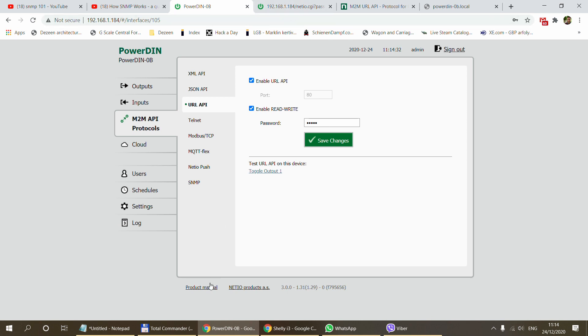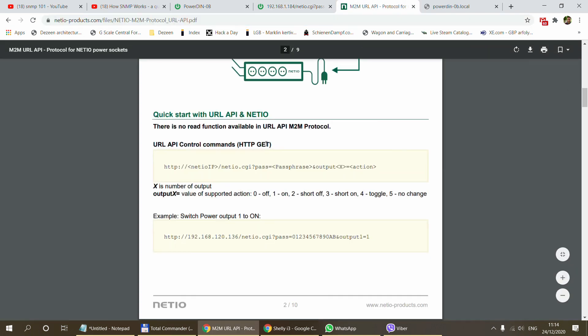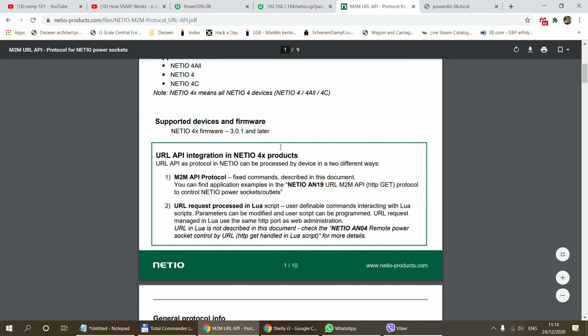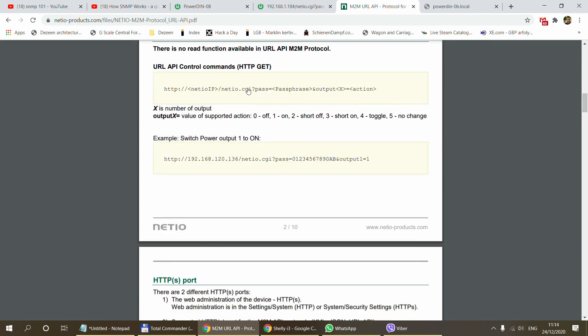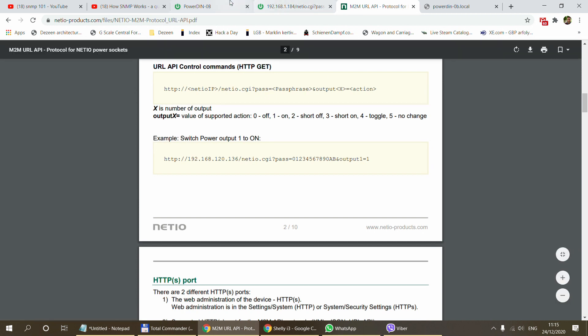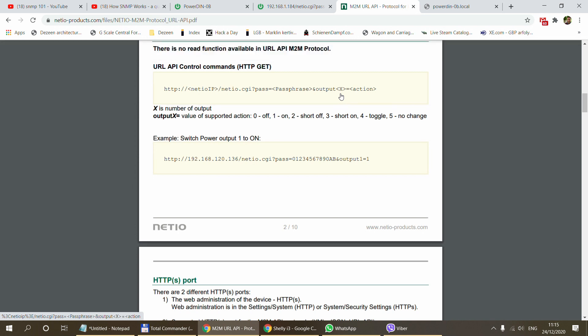If you go into the product website, you can also download documentation about the URL API. The only thing we are really interested in is this example. The way we are going to control the device is by calling a URL, which is HTTP colon slash slash the IP of the device, slash netio dot CGI question mark pass equals the passphrase, and then output x. We are using the PowerDin, so we have four outputs, and this x can be one, two, three, or four — it's indexed from one, not zero.